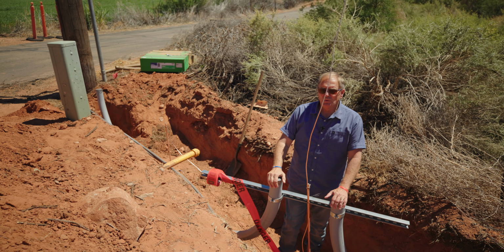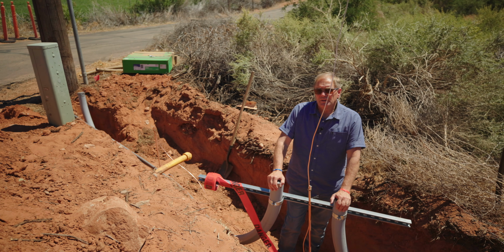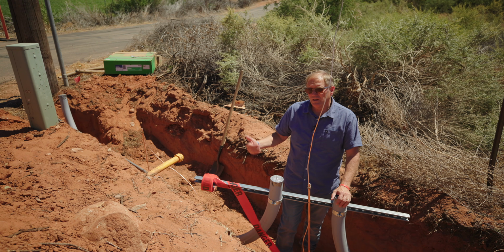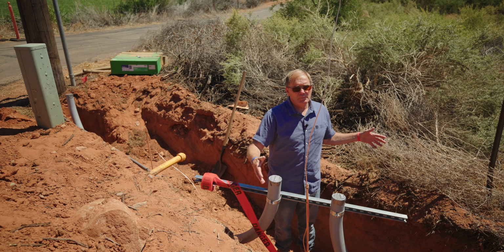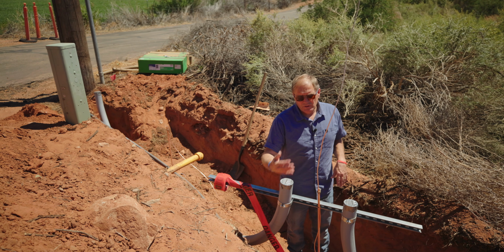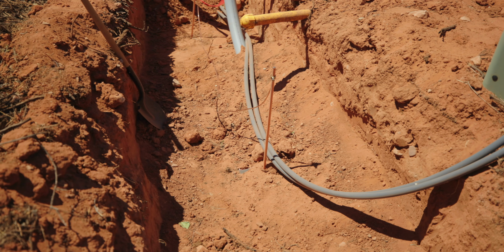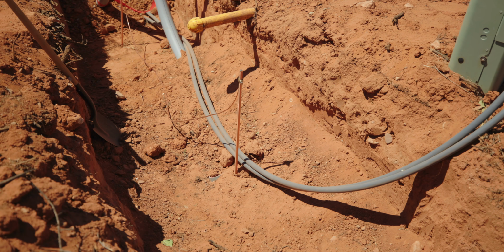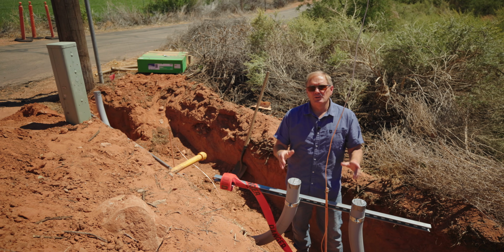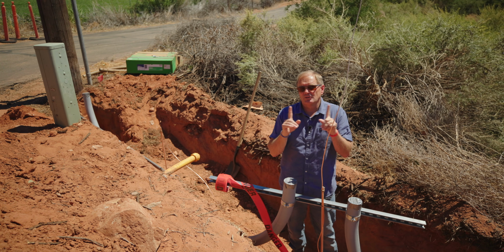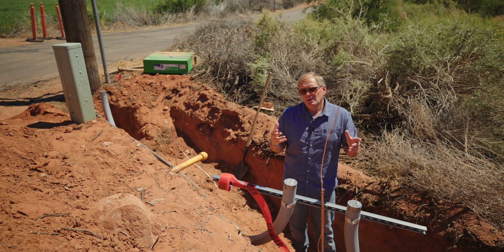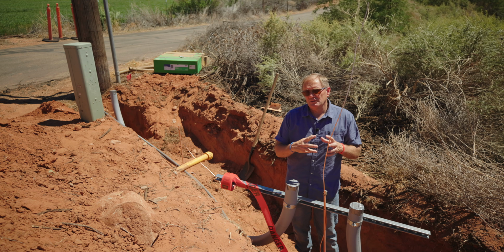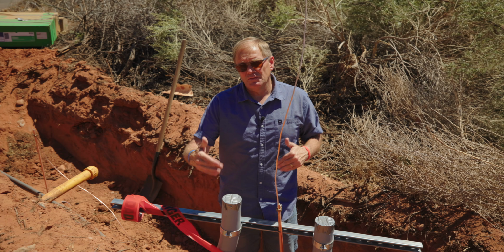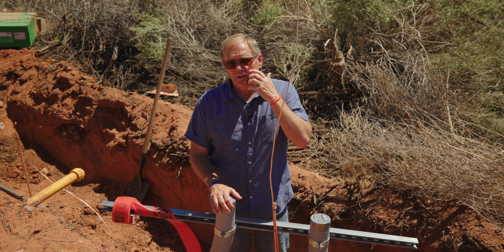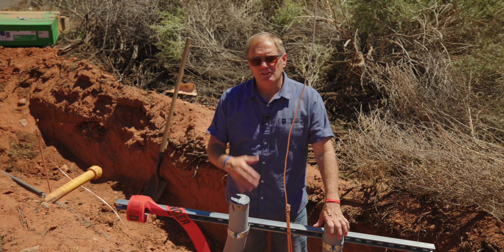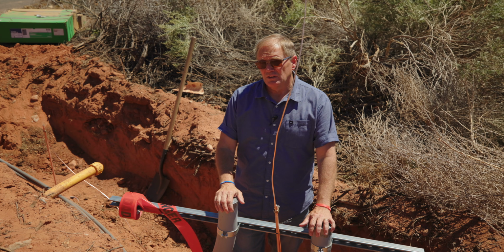Typically they have some issues with running conduit too close to high voltage—one's high voltage, one's low voltage. We kept them apart; this was a 3-foot trench, and we kept the low voltage about 2-plus feet away from the high voltage so there's no interference. It's kind of like Ghostbusters—oh no, we don't want to cross the streams. Don't cross the streams, same idea. You don't want to bring those two too close together. Keep them apart at least a foot to keep down any interference, though a lot of cable now has insulation on it anyway—still something nice to factor in.